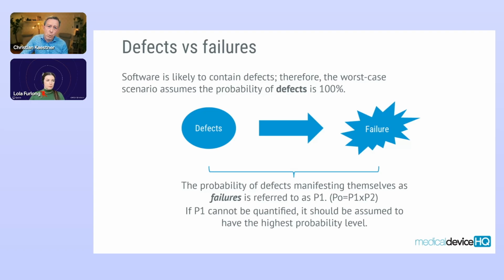If you have evidence supporting that your IEC 62304 development process consistently delivers software with low occurrences of failures, that is an indication that the number of defects is low and hence could be used to claim a P1 less than 100%. However, if you don't have supporting evidence, you should assume the worst case scenario for the process rigor level determination.